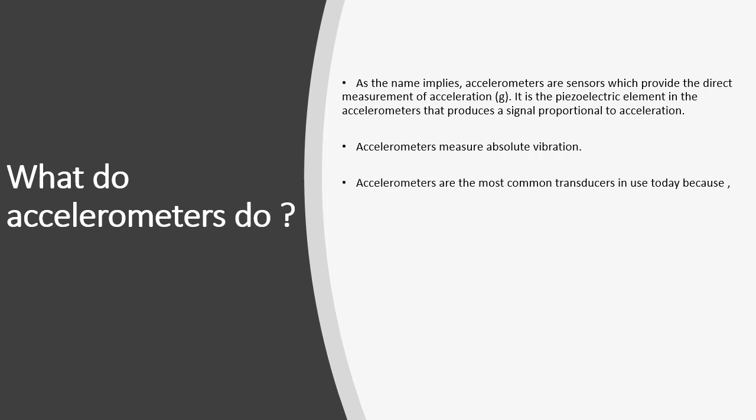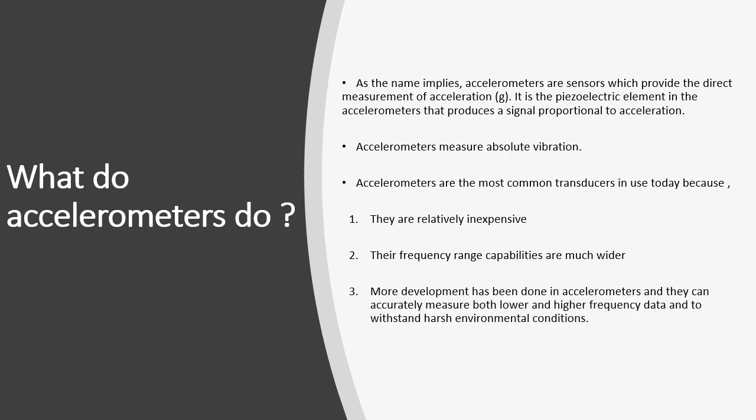Accelerometers are the most common transducers in use today because of various factors. They are relatively inexpensive compared to the other vibration transducers, and their frequency capabilities are much wider to take care of various testing conditions and applications. There has also been more development in accelerometers, and they can accurately measure both lower and higher frequency data and can withstand harsh environmental conditions.